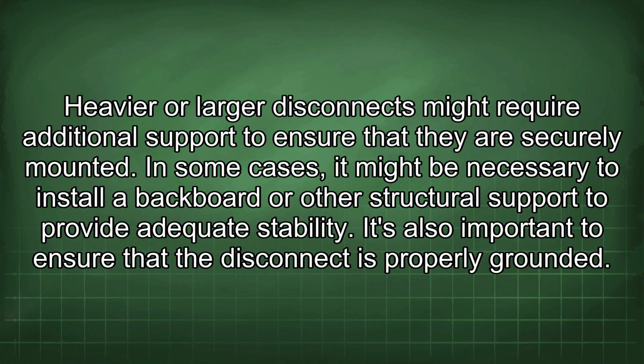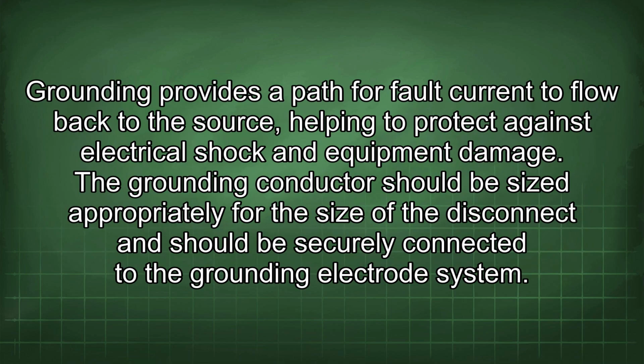It's also important to ensure that the disconnect is properly grounded. Grounding provides a path for fault current to flow back to the source, helping to protect against electrical shock and equipment damage. The grounding conductor should be sized appropriately for the size of the disconnect and should be securely connected to the grounding electrode system.